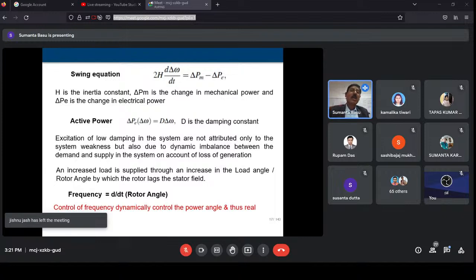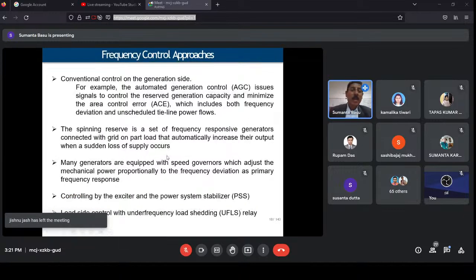All of us are aware of how grid inertia is related to the machines on the grid. It is governed by the swing equations, and the active power delivered by the machines is related to the rotor angle, and frequency is nothing but the rate of change of the rotor angle. So what does AGC do with respect to this?